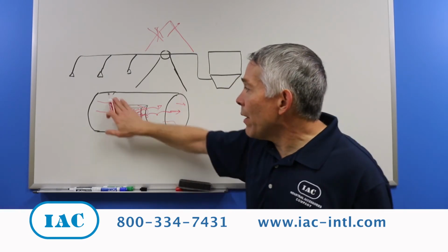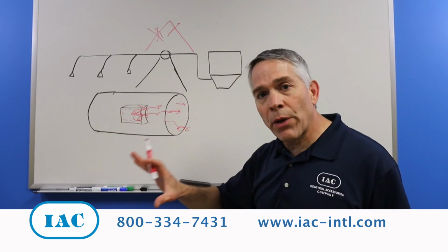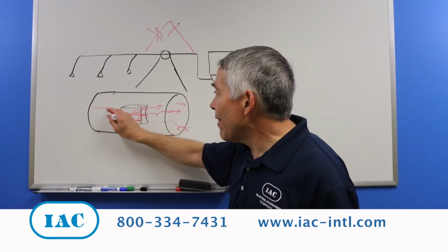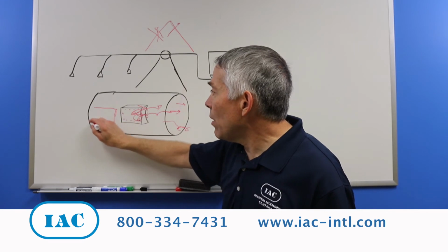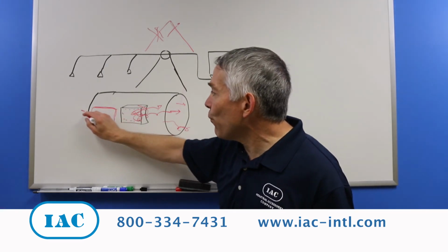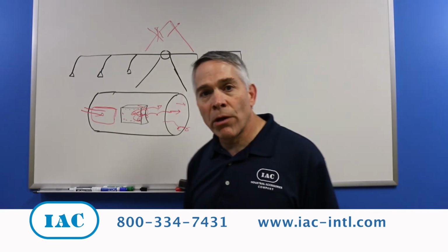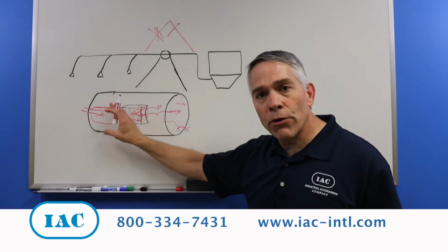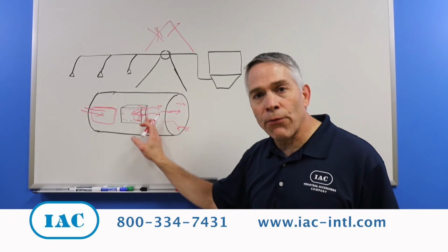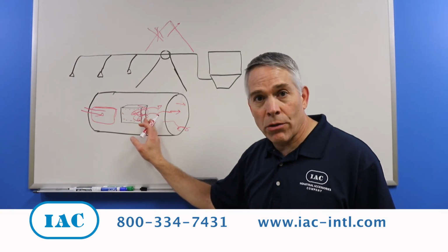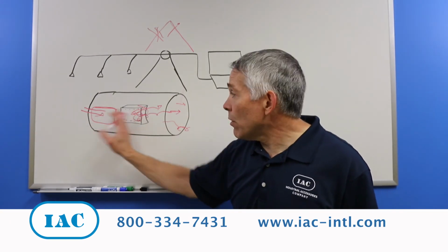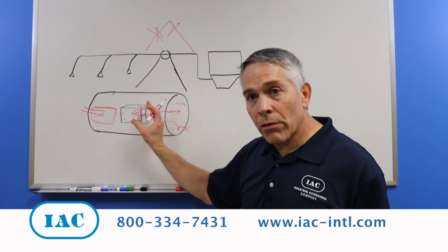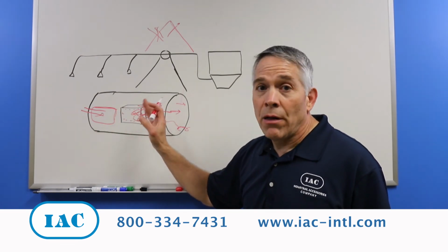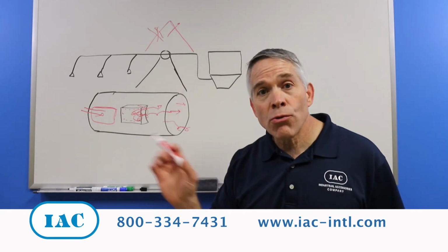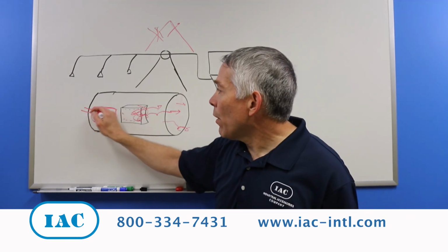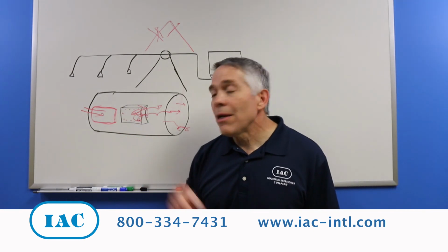So what we recommend when you have horizontal ductwork is to put inspection doors, but there are inspection doors that mold to the shape of the ductwork so that airflow moving inside is not disrupted. These are readily available off the shelf, and yet we see this bad design often, which is very bad for your ventilation system. So you can contact us to discuss what options you have, but inspecting horizontal ductwork should be done on a periodic schedule, using the proper access doors to minimize losses.